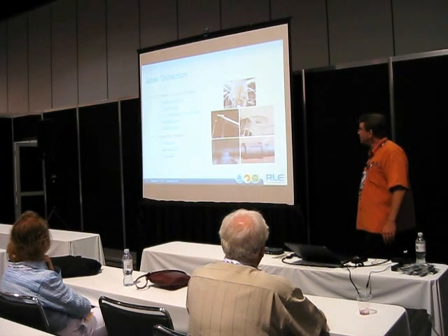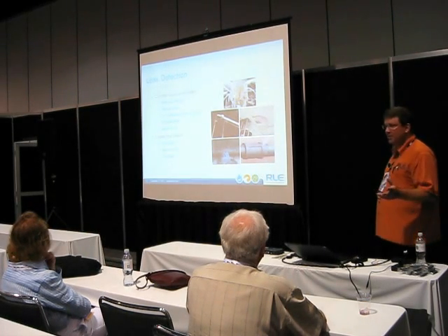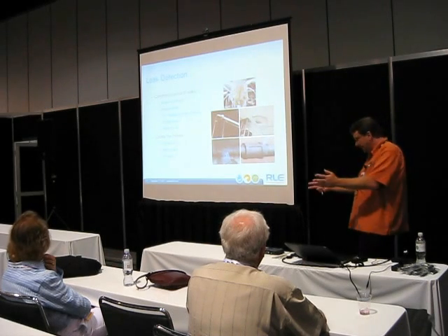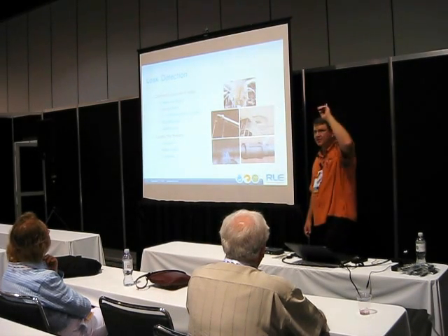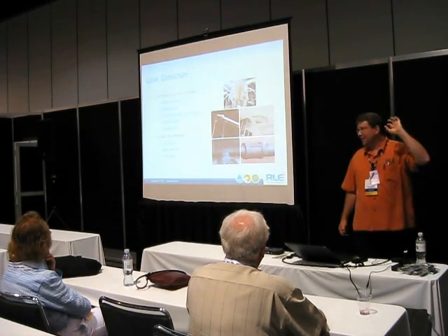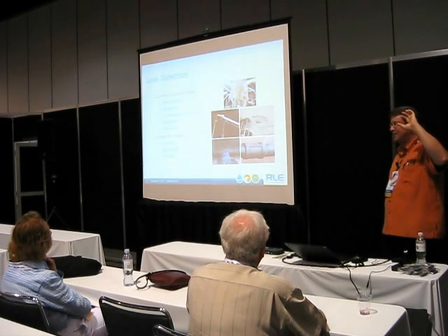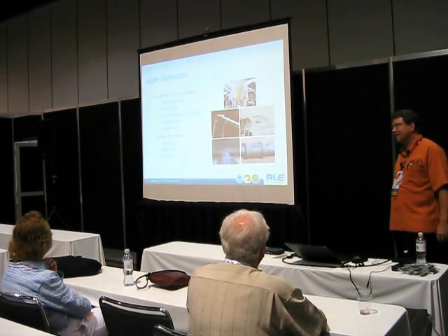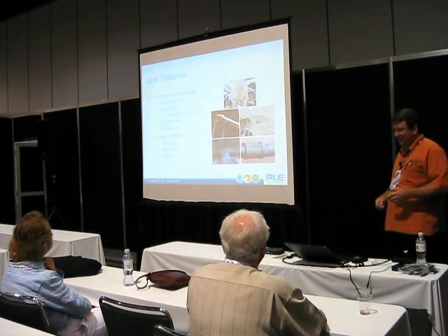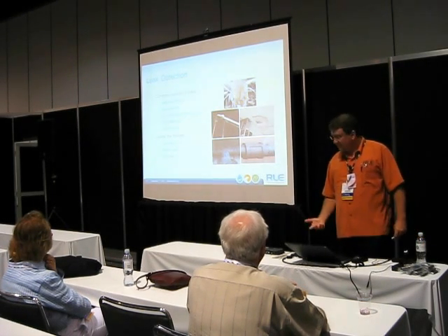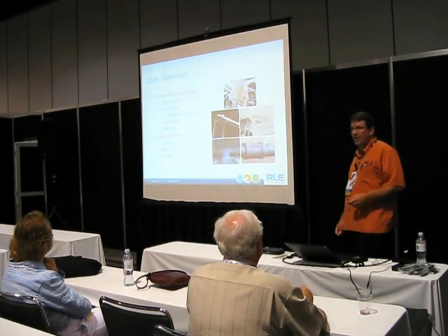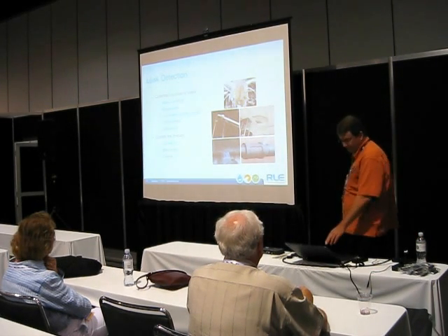So as far as common sources of leaks, I talked a little bit about it. But when I walk into a building, the first thing I do is look around. Most people kind of walk like this. I'm actually looking at the ceiling as I'm walking through that building. And you see all those telltale brown stains all over the place. That's the start of something. And identifying that, what can we do to identify that before it gets real serious? Certainly locating those threats on the floor, behind walls, overhead, but thinking about the big picture.